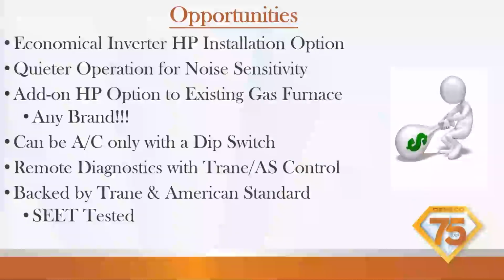So it's an economical inverter, so it's cost efficient. It's a good quiet system, and you have an add-on heat pump option to an existing gas furnace, any brand. So that's kind of nice. You can slap a coil under any existing furnace. I do recommend always swapping out a furnace if they're going with the new system, but if they got a 4-year-old furnace, then so be it. Can be AC only with the dip switch. So if you just want an AC, you're going to set it with a dip switch, and it's just AC, no heat pump. So you'll keep the gas heat with AC.